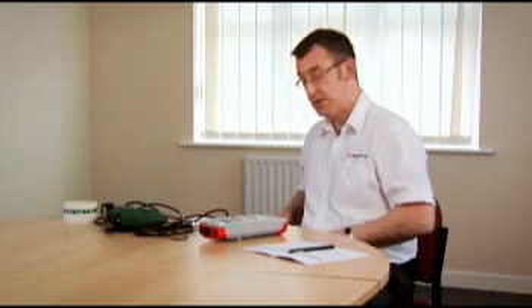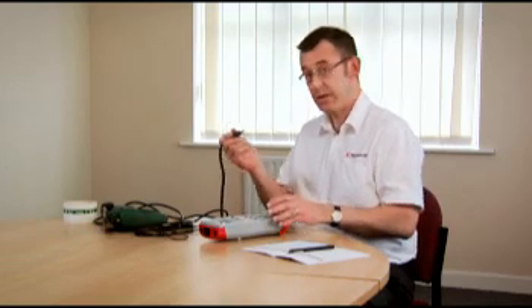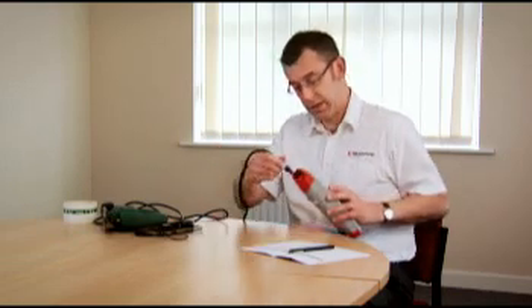Now we're going to test a Class 2 appliance. This time we're going to do a power leakage test rather than the substitute leakage using the internal power supply. So we need a mains supply to do that. We connect the mains power into the top of the tester.